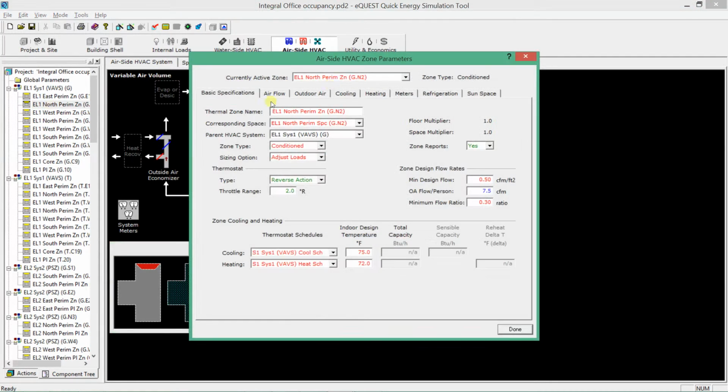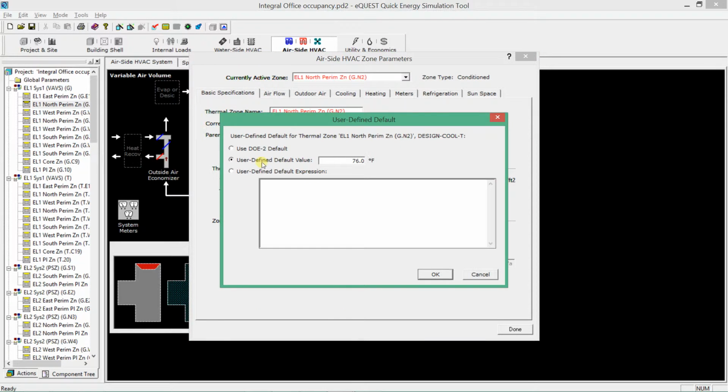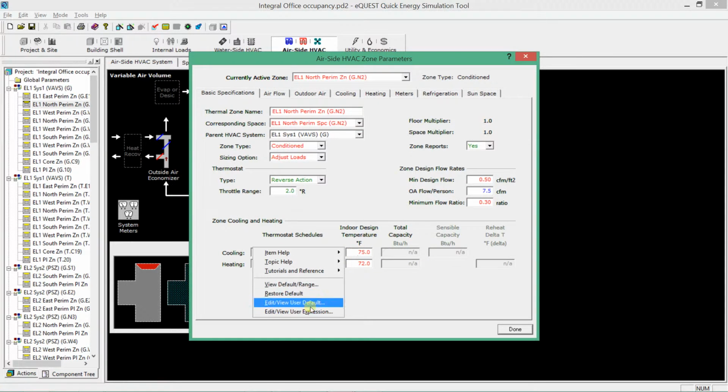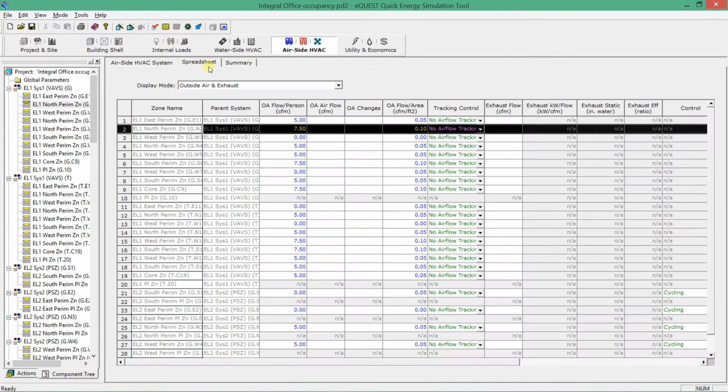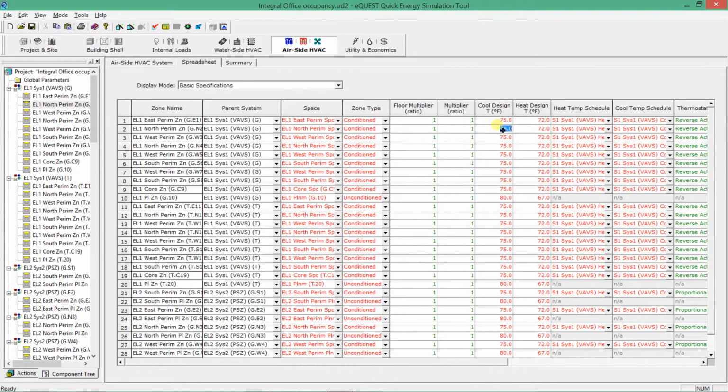And the last piece for ventilation that we're going to set up, actually, some of the things we could just do really quick. We could also start to change the thermostats. So I just pasted in the same set of equations, but now let's say that conference rooms are 75, corridors 75, open office 75, mechanical rooms, maybe those can be 78, and the default will be 75. So, you know, you can just start to add in better code throughout your building, wherever you have time to walk around and make changes.